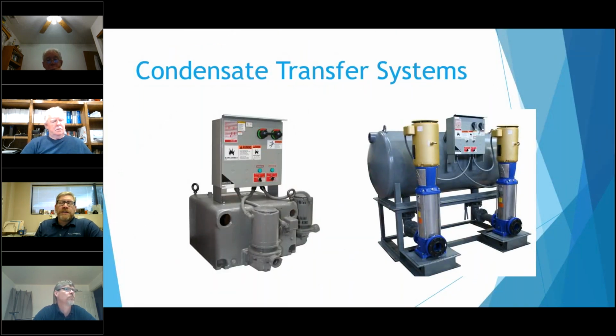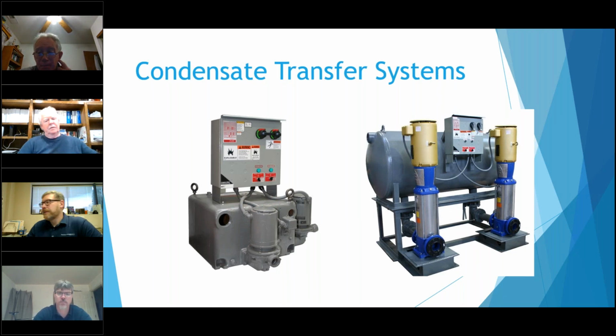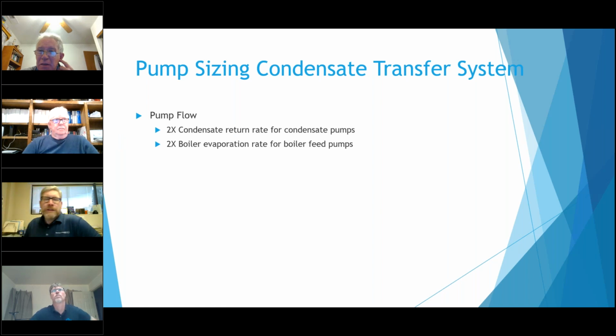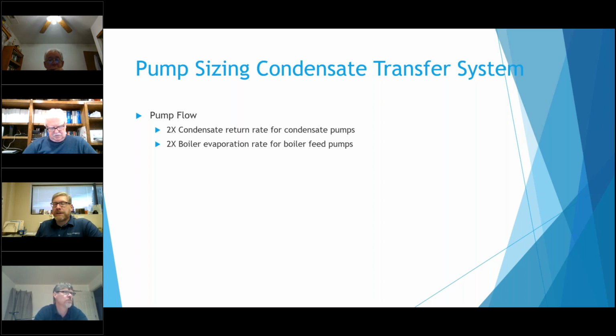Some of the other things that pumps are used on, other than just plain hydronic systems, are condensate transfer systems, whether you've got just a condensate pump itself or more of a boiler feed unit. They're sized fairly similar in that you're doing 2 times the return rate, but it's where that return rate comes from. Condensate units are usually sized on 2 times whatever is getting dumped into that condensate unit. That way you've got enough pump flow to get the water out before it overflows. For boiler feed units, it's the boiler evaporation rate. You want to make sure the pump can put in twice the amount of water into the boiler that it requires. That way, you're not going to put it in a low water condition or anything like that.